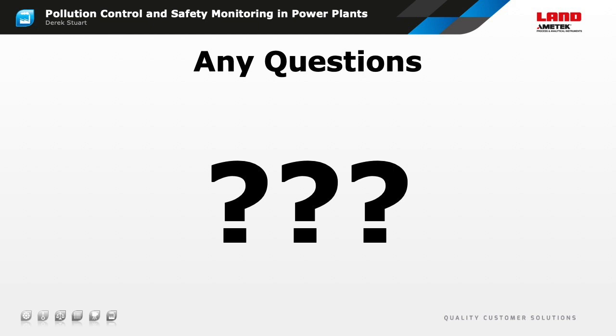So in general, I would not recommend doing without air purge, and absolutely definitely not for any optical components that are being used for compliance purposes where your site operating permit absolutely requires these things to be operating correctly.